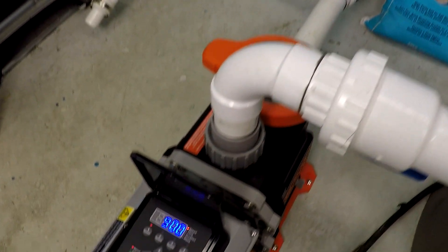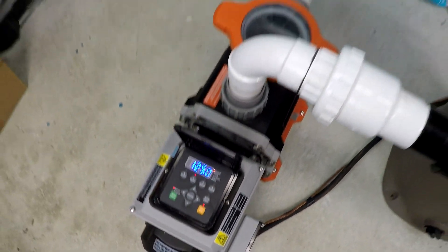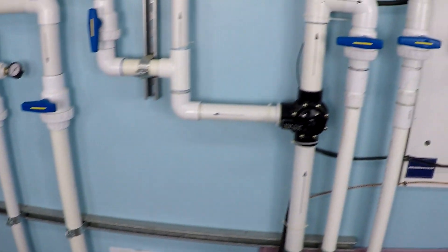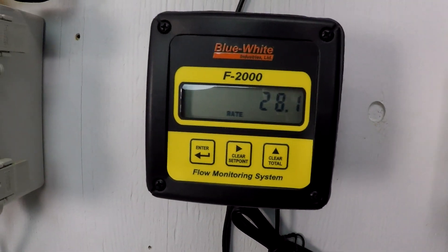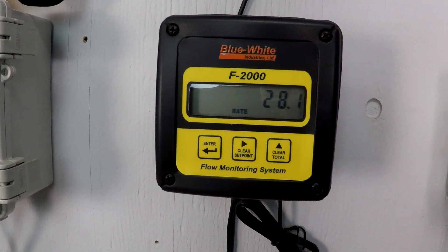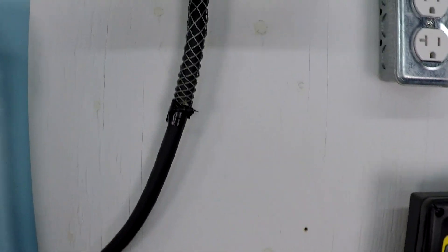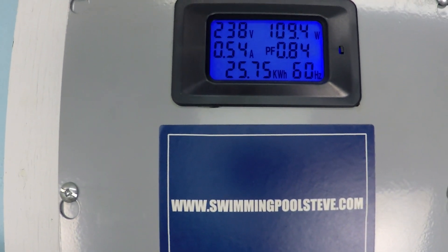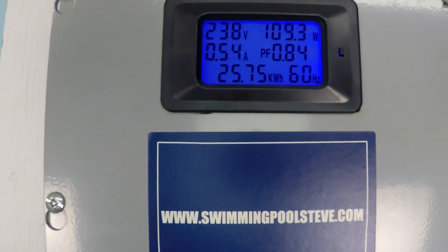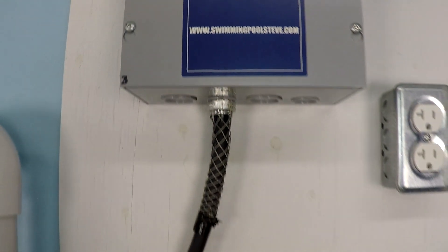Let's increase the RPM a bit here to 1250. At this speed we're seeing just about 28 gallons per minute, 109.4 watts of power consumption, and 0.54 amps of current draw.